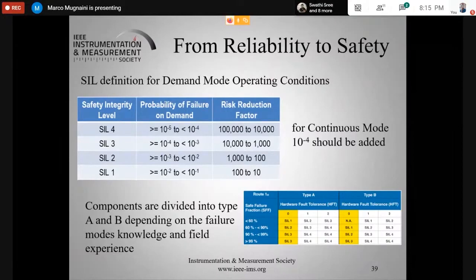It's not exhaustive, and here you have some constraints, looking at the yellow columns. If you have a hardware fault tolerance of zero, meaning once your system is broken you lose the safety function, with a type B component you can get a lower SIL level than with a type A component - for example SIL 2 versus SIL 3. So with brand new components, you have higher constraints than with well-known components.